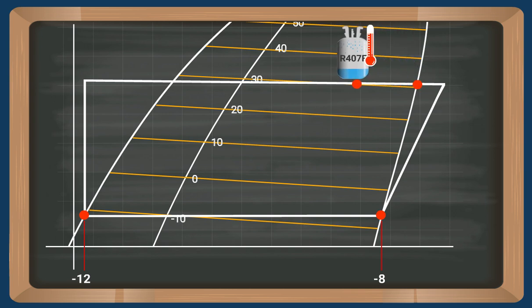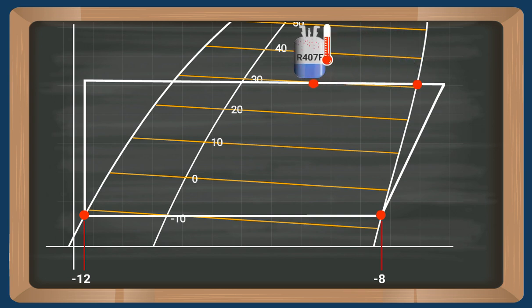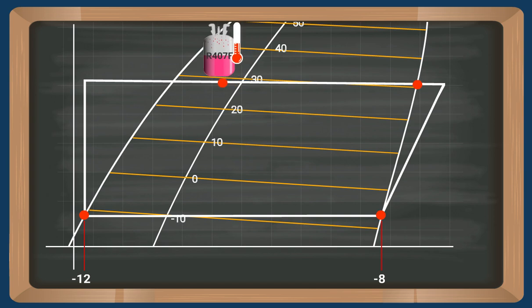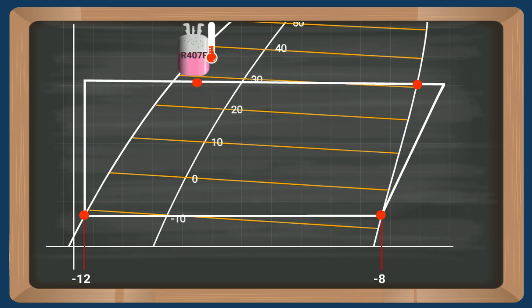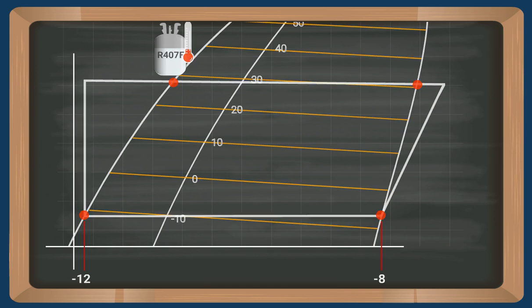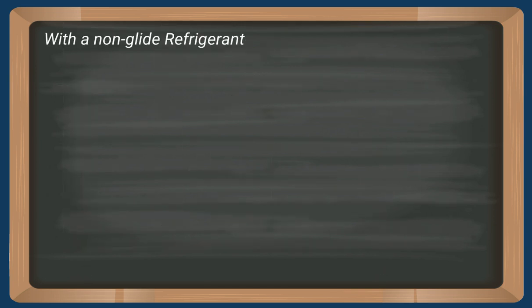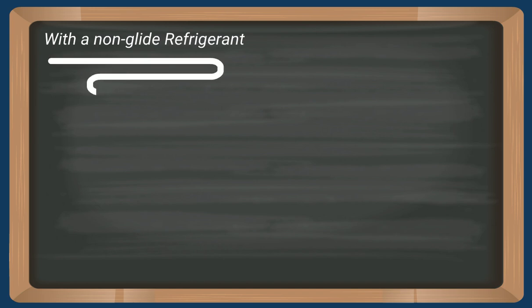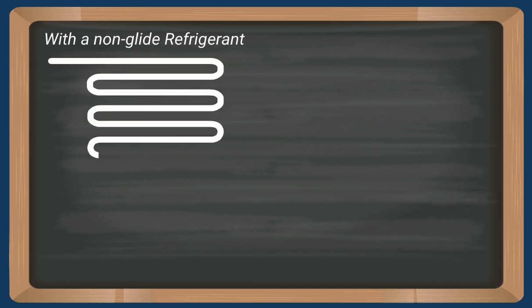The condensing process follows the same pattern, just opposite. The first component to condense is the R134A, then the R125, and then finally the R32. All this has, of course, consequences for the superheat setting.